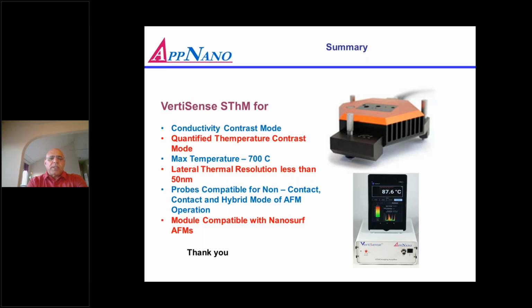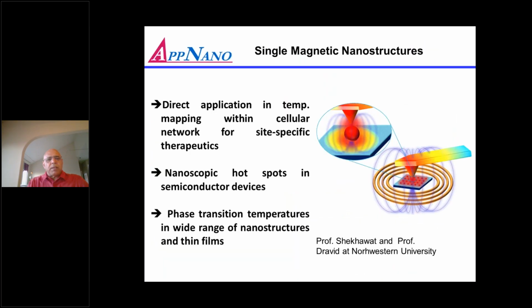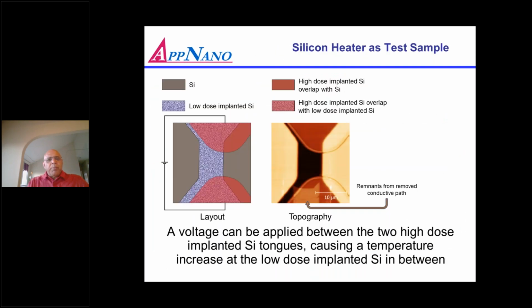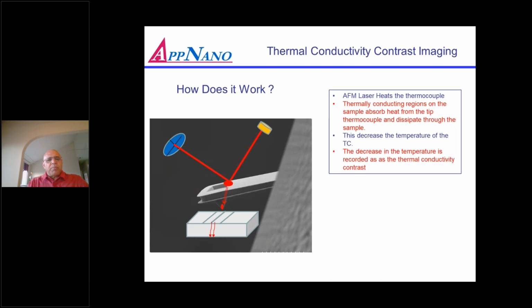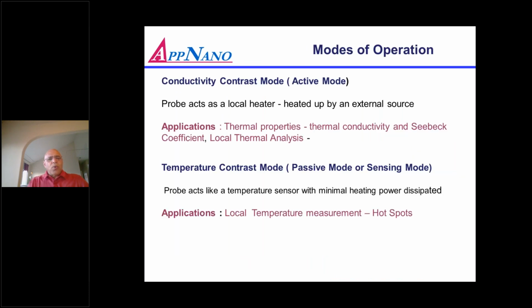Then you can use these probes in a contact mode, non-contact mode, or hybrid mode of operation depending upon your applications. Sometimes in the hybrid mode people want intermittent contact with the sample, so you can do that also. All this unit is compatible with the AFMs from Nanosurf with the mounted probes, and they have a specialized holder which can go with their AFMs. Their laser is excellent. They get beautiful images with the thermoelectric contrast. With their new drive AFM, which is very exciting, I want to show you this because when I saw this image of the drive AFM, especially that has an inbuilt laser, I don't know if you have all the data or not, but that's very attractive for heating the whole thing which we are talking about.